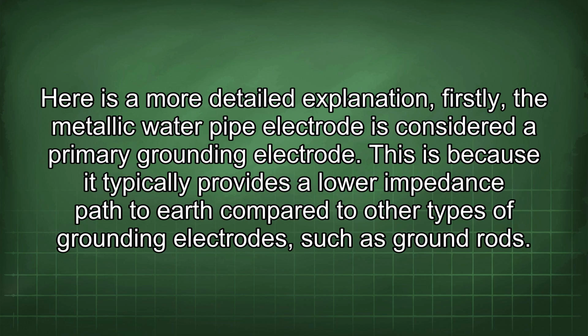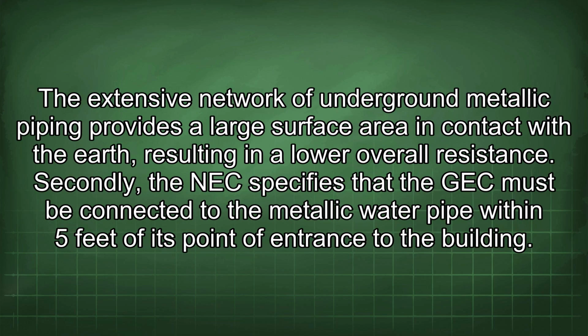Firstly, a metallic water pipe electrode is considered a primary grounding electrode. This is because it typically provides a lower impedance path to earth compared to other types of grounding electrodes, such as ground rods. The extensive network of underground metallic piping provides a large surface area in contact with the earth, resulting in a lower overall resistance. Secondly, the NEC specifies that the GEC must be connected to the metallic water pipe within 5 feet of its point of entrance to the building.